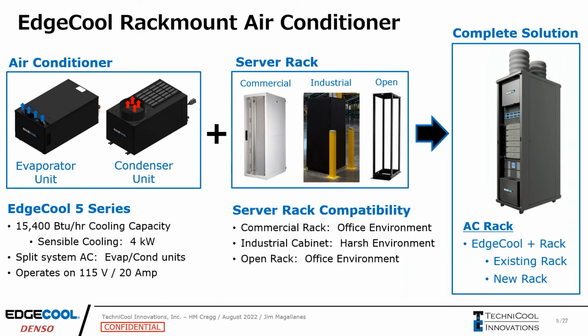And what is the EdgeCool rack mount air conditioner? Well, it's a split system air conditioner, meaning it has two different components, an evaporator unit and a condenser unit. And the cooling capacity is 15,400 BTUs with a sensible cooling of about 4 kilowatts. It operates on 115 volts and a 20 amp circuit. So it has that 5-20 plug on there.